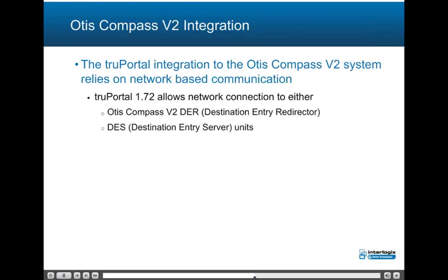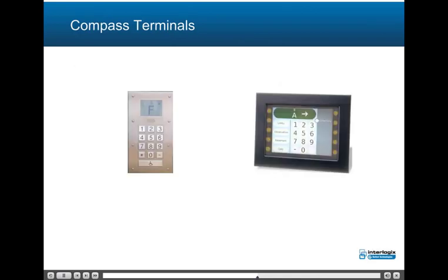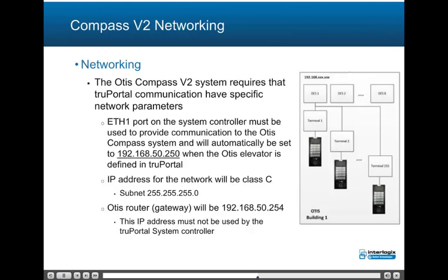The second elevator solution is the Otis Compass V2 integration. The truPortal integration to the Otis Compass V2 system relies on network-based communication and will be handled by a joint collaboration between the truPortal installer and Otis Elevator technical installers. truPortal 1.72 allows network connection to either the Otis Compass V2 DER (Destination Entry Redirector) or the DES (Destination Entry Server) units. The Otis Compass V2 system topology includes a single DES or multiple DES units communicating through a common DER; the DEC is a user terminal at the entrance to a particular elevator or bank of elevators. Networking requires that truPortal communication use specific network parameters.